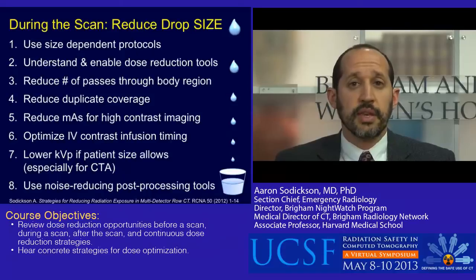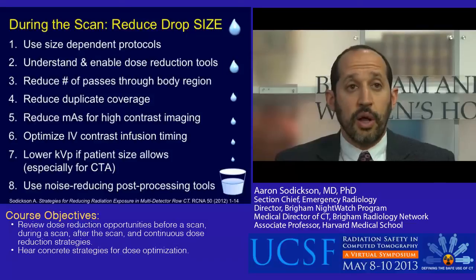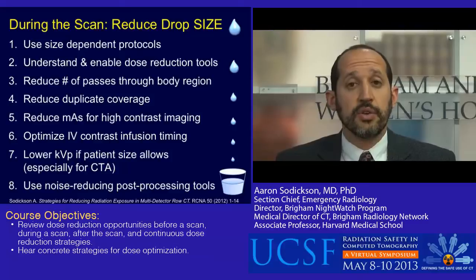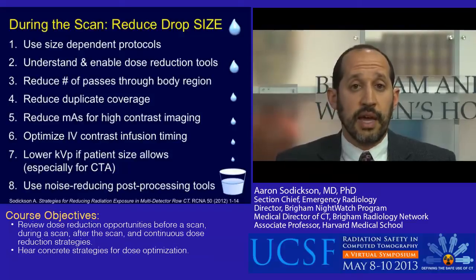Now, this can be a computationally intensive and time-consuming process. So all of the different manufacturers have different variants of iterative reconstruction and have taken different algorithmic shortcuts to speed this process up. But the end result is that these techniques can reduce noise or can reduce artifacts or both. The caveat is that they do create different noise textures, and so radiologists often need some time to acclimate to the different image appearance in order to find that comfort zone for the diagnostic task at hand.